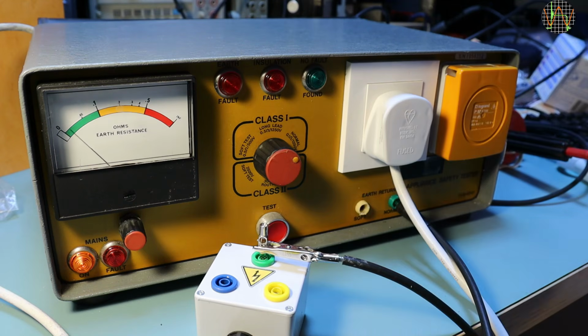And it fails. The meter still shows we are well in the green zone, so it should not fail. Not sure what's going on there. Maybe the unit needs to be recalibrated. I noticed that my white cable and the UK plug are quite warm already.